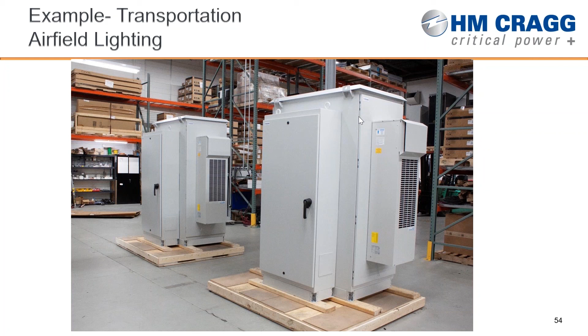Hot, humid environments, a lot of heat being thrown off of the UPS. So we've got 13,000 BTU air conditioners installed. And then a similar situation with the hydrogen sensor, hydrogen vent kit, and temperature actuation on the back side of the enclosure. There it is, yeah.